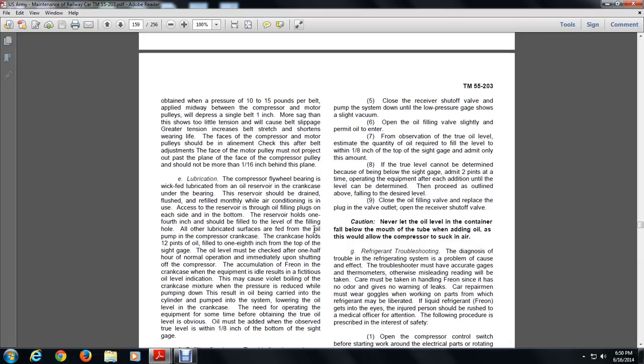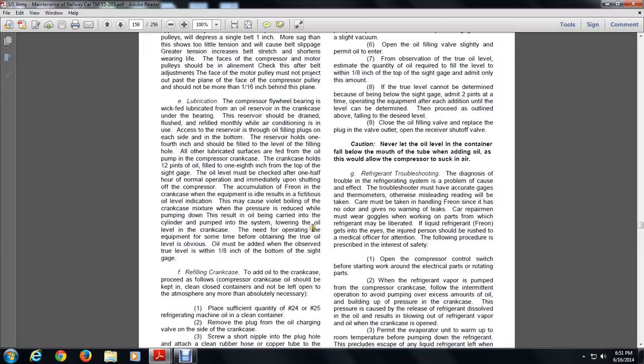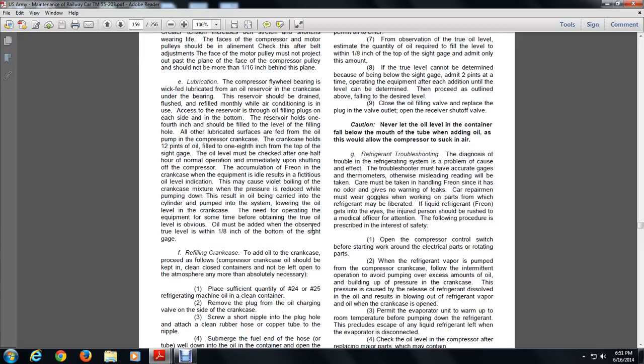Excessive tension increases belt wear and shortens its life. After belt adjustment, the face of the motor pulley must be in alignment with the face of the compressor pulley and should not project more than 1/16 inch behind that plane. Lubrication: The compressor flywheel is lubricated by a wick-fed system from an oil reservoir in the crankcase bearing. The reservoir should be drained, flushed, and refilled monthly while air conditioning is in use. The reservoir holds one-fourth inch of oil and should be filled to the level of the filling hole.